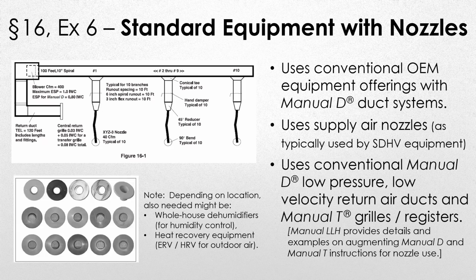So as time goes on, in order to deal with the low airflow issues, we think that this example will probably be the most utilized, next to probably small duct high velocity systems, possibly. But now that this manual is out and it shows you how to use nozzles on a conventional system, we think this probably will take up more of the market and be more accepted. One of the reasons this works now is that more upscale equipment from manufacturers can handle higher static pressures. Some residential equipment where we're used to only being able to handle 0.5 inches of static can handle up to 0.8 or a whole 1 inch of static. So not every furnace or air handler will work with this system. You need to pick one that'll have higher static ability.